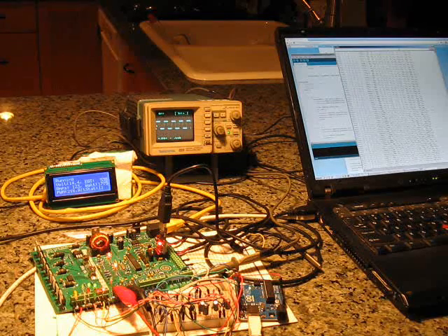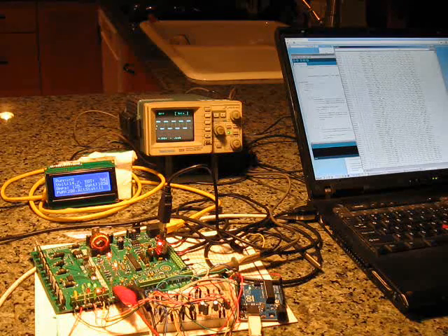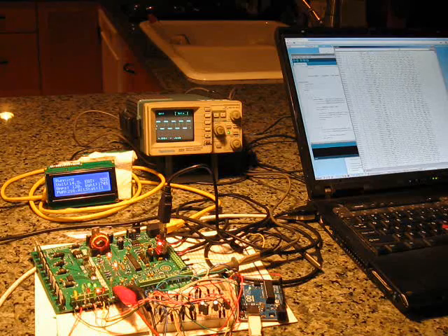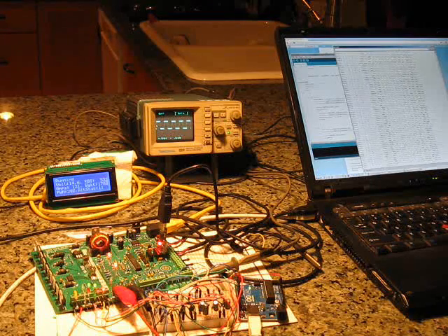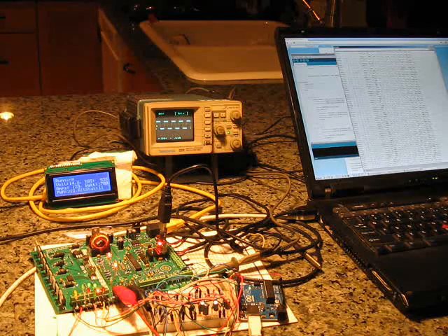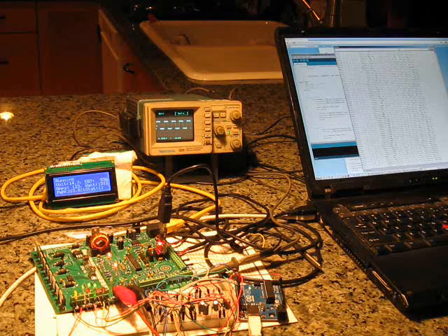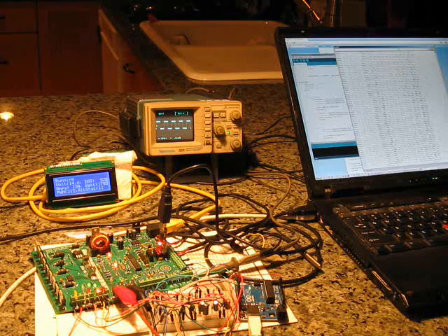At this point, we've entered the acceptance phase. Because of the simulation here, it actually ends up skipping over the bulk phase. We have condensed everything down in a very short period of time, so we end up skipping over the bulk phase. The simulator continues to accept the charge, and the battery continues to raise the battery voltage.